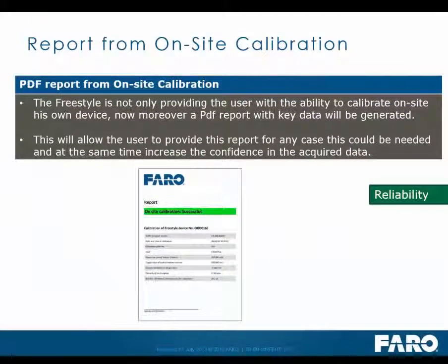We now give you the ability to create a report, so if you're doing on-site calibration, which you can do with the calibration plate supplied with every unit, you can then print a report to validate the data that you've scanned.